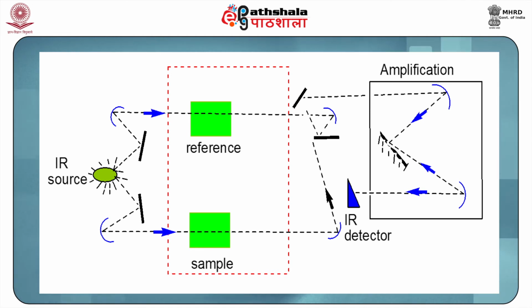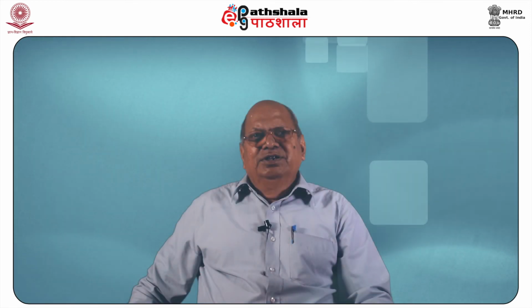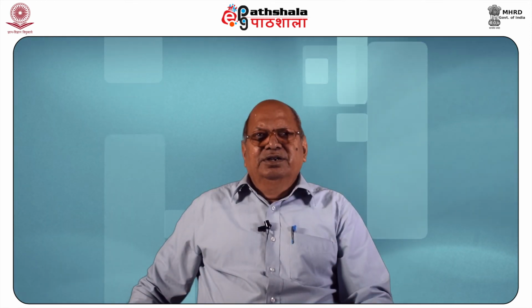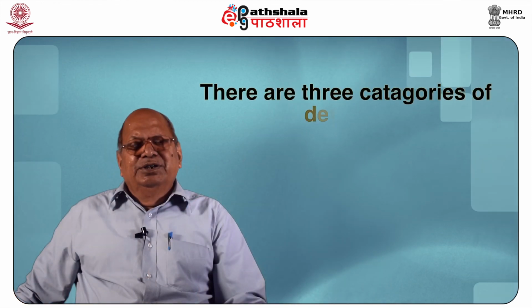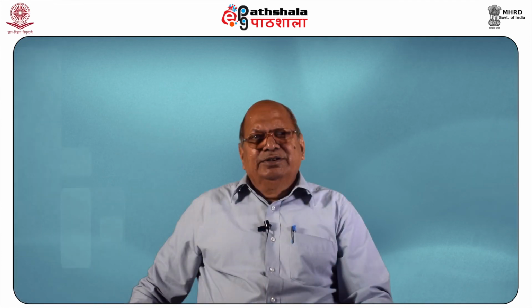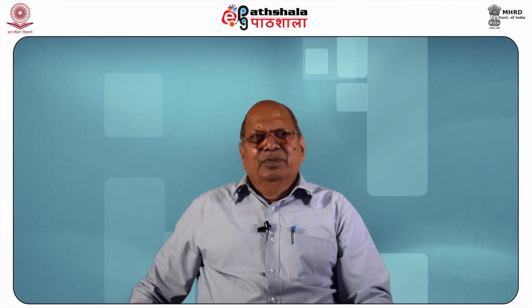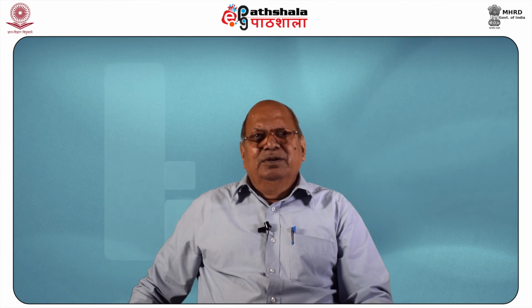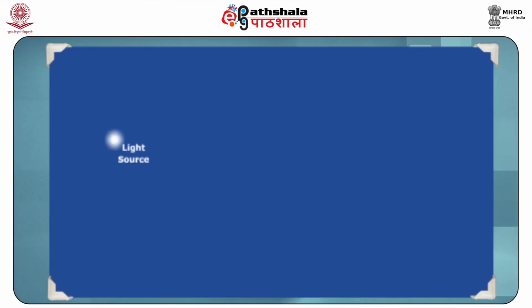Now, the IR radiation from the source, after reflection at a flat mirror and rotating mirror, passes through the reference and sample. The transmitted light is amplified and detected by the IR detector. There are three categories of detector: thermal, pyroelectric and photoconducting. Again, this will not be part of the discussion.